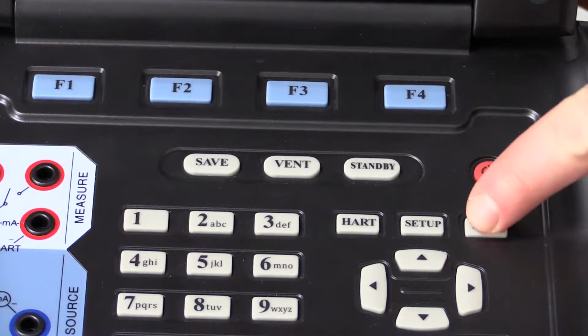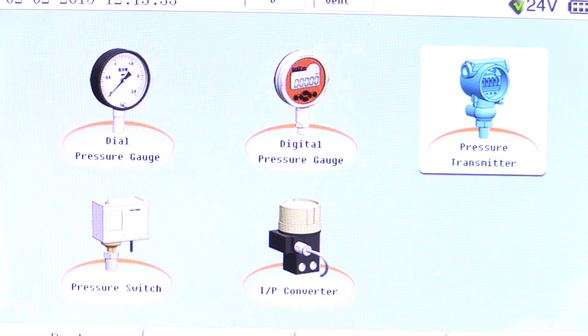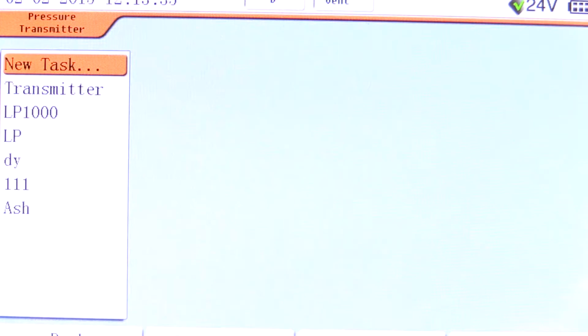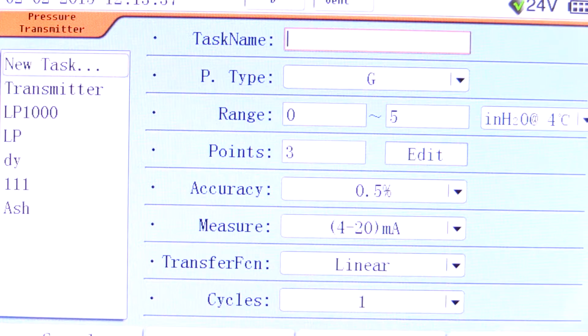Press the Task button and select Pressure Transmitter. Tasks are automated calibration procedures stored in the ADT761 memory. New tasks can be created or old tasks can be renamed or modified. Each task has a unique name and various fields specific to the device under test. When all the information is entered, the task can be run.